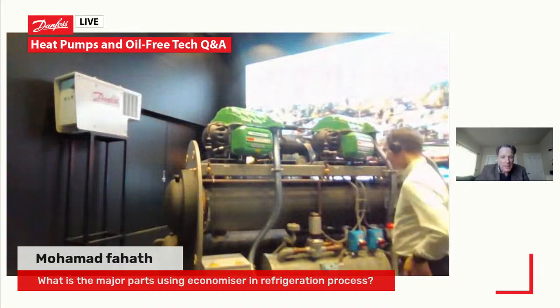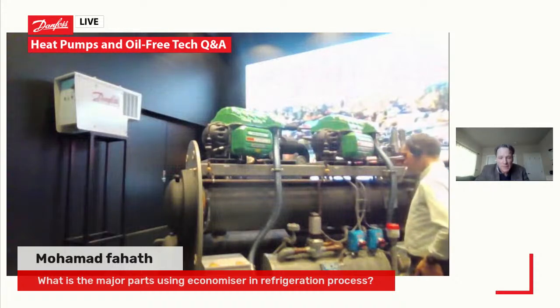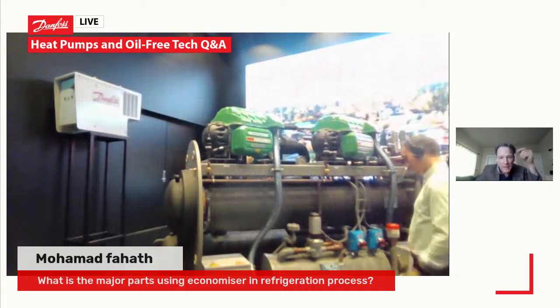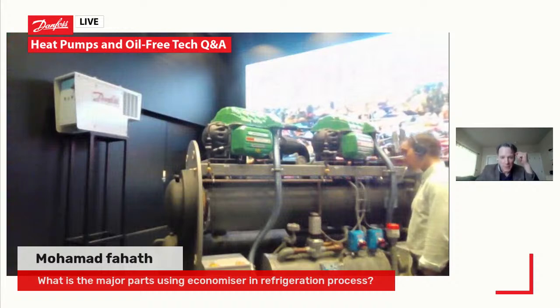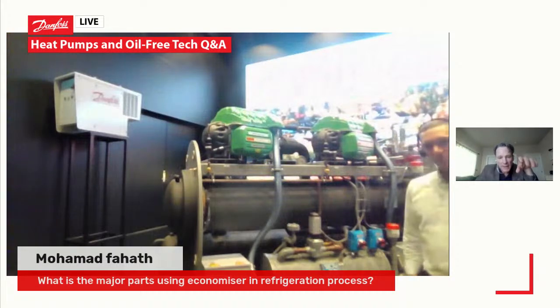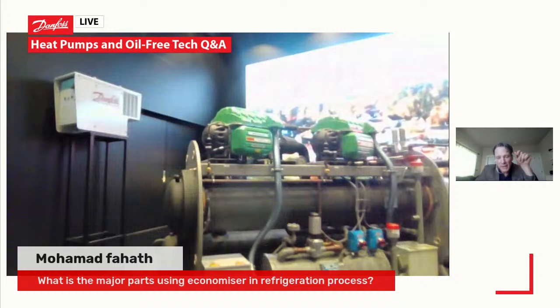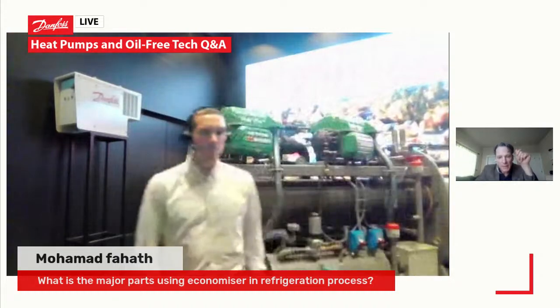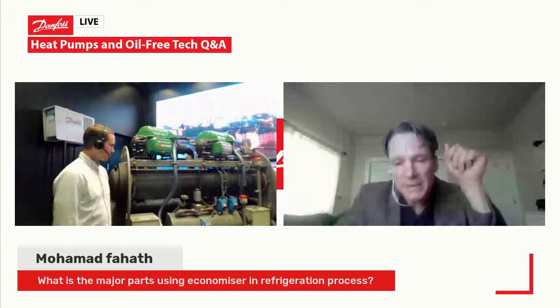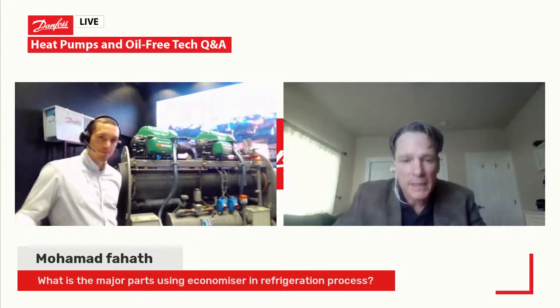So that right behind Jonas is a flash tank economizer system used on the NG chillers applied in the Danfoss headquarters building in Nordborg. That's a flash tank economizer system. To answer your question, the components utilized in a flash tank economizer system are somewhat different from those used in a brazed plate heat exchanger economizer system. A brazed plate or microplate heat exchanger economizer system is more compact, but has a slightly higher approach temperature, so the performance will be a little bit less.